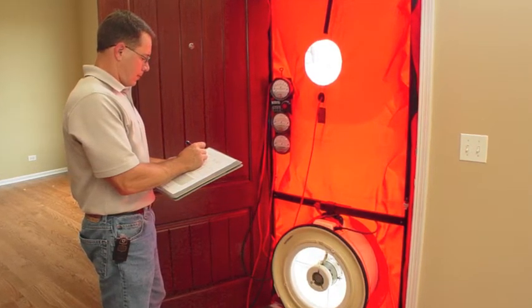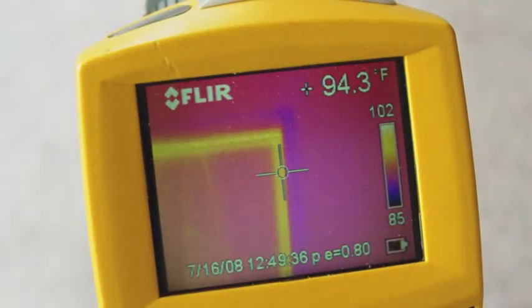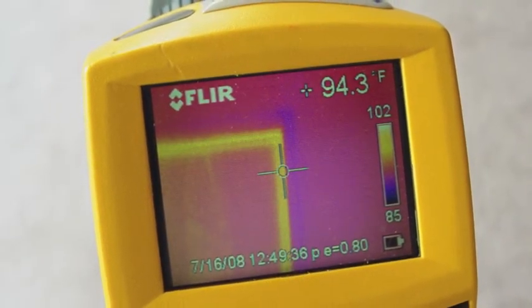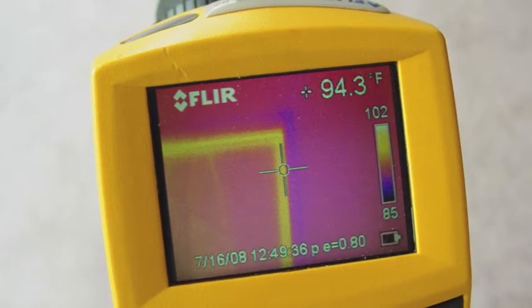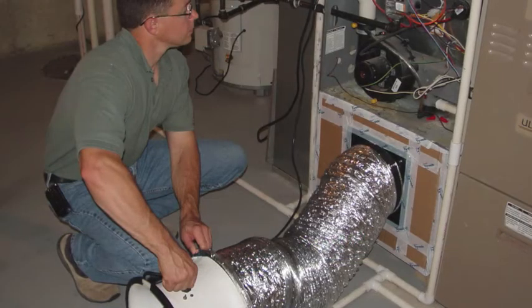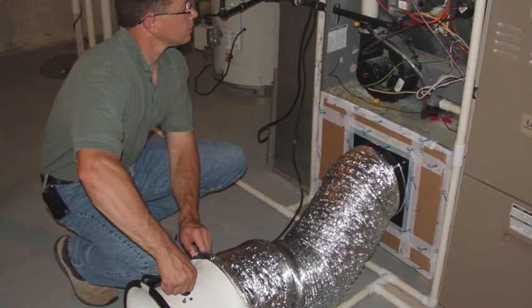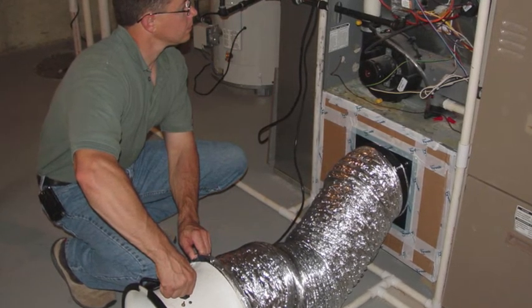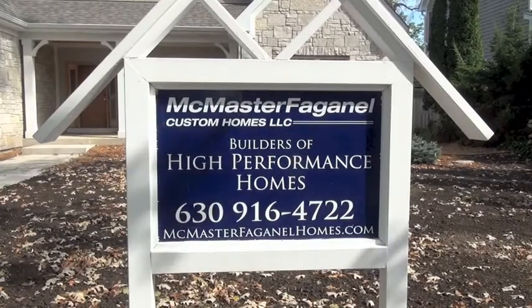Why don't you talk a little about what you do for us in terms of testing and what the advantages are? All the testing we do is just to verify that everything's done as it's supposed to be. In addition to the blower door and infrared camera, we're also testing ductwork these days, making sure it's substantially tight with no leakage, getting the airflow to the rooms where it's intended. We're also looking at airflow in individual rooms, measuring airflow from each register and testing individually. We test the bath fans too, making sure there are no kinks or obstructions in the lines, so you're getting the full amount of flow from those fans, which eliminates moisture problems and other issues in the bathroom.